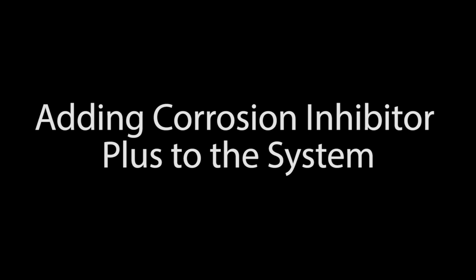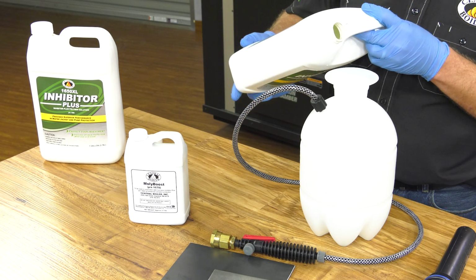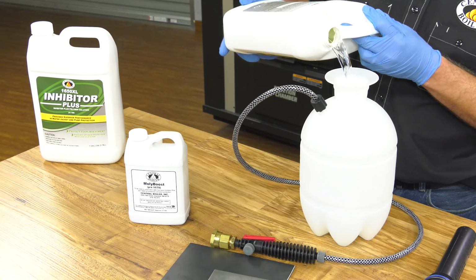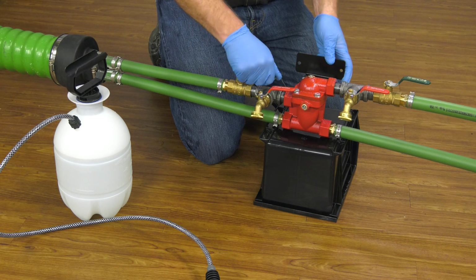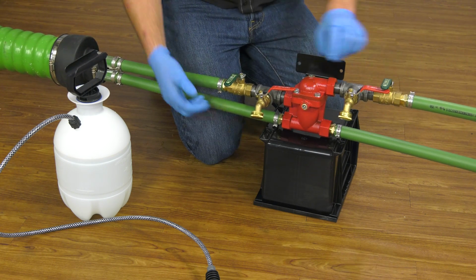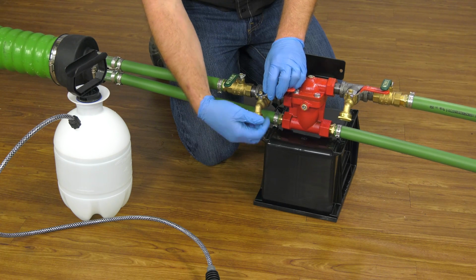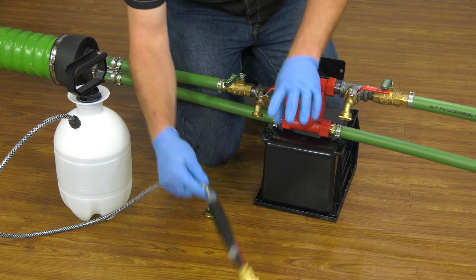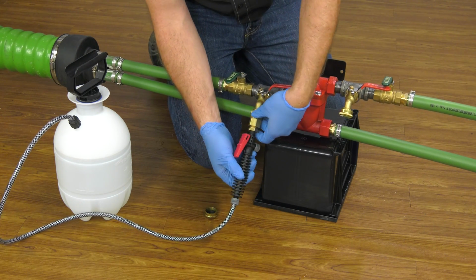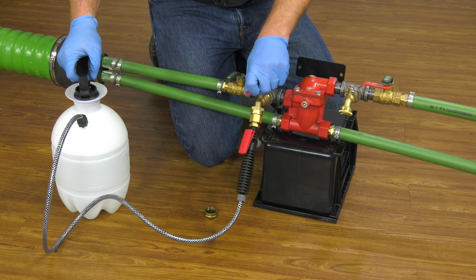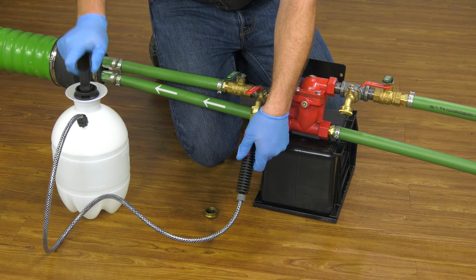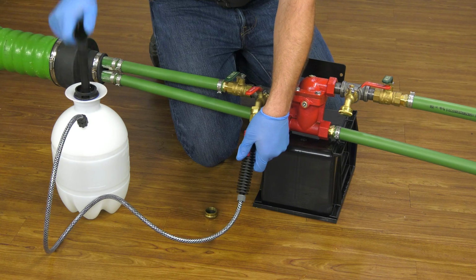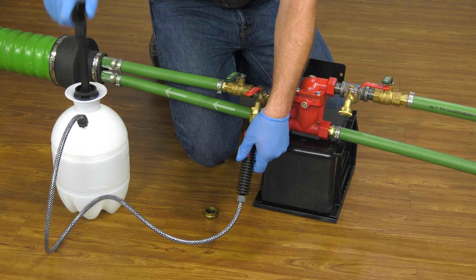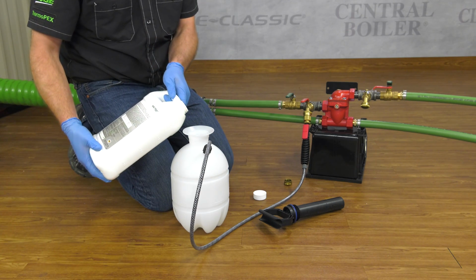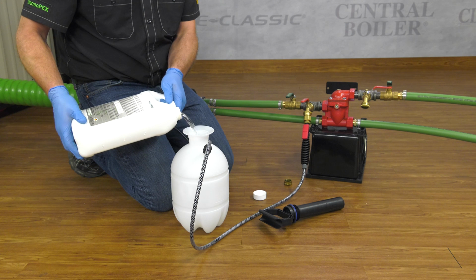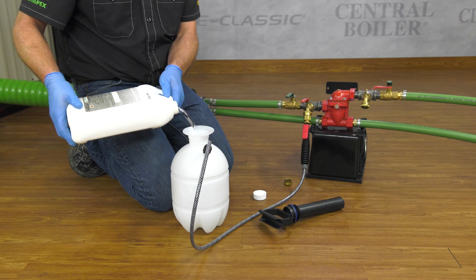Start by adding 1 gallon of Corrosion Inhibitor Plus in the pump jug that's available from your central boiler dealer. Close these 2 valves near the thermostatic valve to ensure the chemical goes back to the outdoor furnace through the return line. Attach the pump jug nozzle to the drain bib and open this valve. Pressurize the pump jug and add the entire contents to the furnace through the return line. If more Corrosion Inhibitor Plus is needed for your furnace model, add it to the pump jug and repeat.